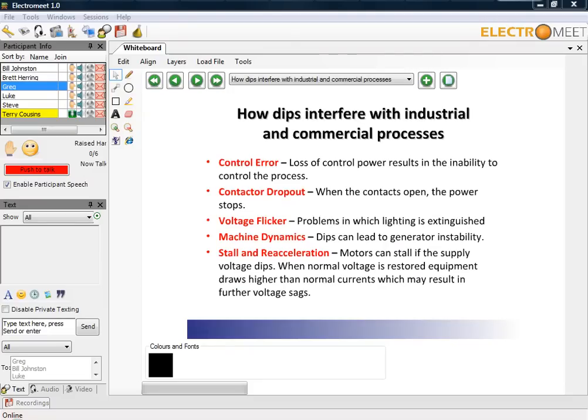How do these dips interfere with industrial and commercial processes? First of all, we can get a loss of control, where the loss of power results in the inability to control the process. We can have things like contactors dropping out, where when these contactors open, power is lost to equipment. We have voltage flicker, which is really anything related to lighting — if there are humans involved, we can't work without lighting.